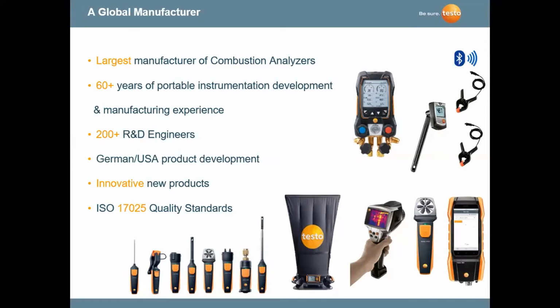One thing to bring up here is that we are ISO 17025 quality standards, and ISO is an international standard where, in our New Jersey headquarters, we have the calibration equipment and the protocol to maintain very accurate measurements on our tools. Every tool that we send out is calibrated to certain specifications, and we're going to be talking a lot about accuracy today, accuracy of digital gauges. I wanted to bring this up to you.